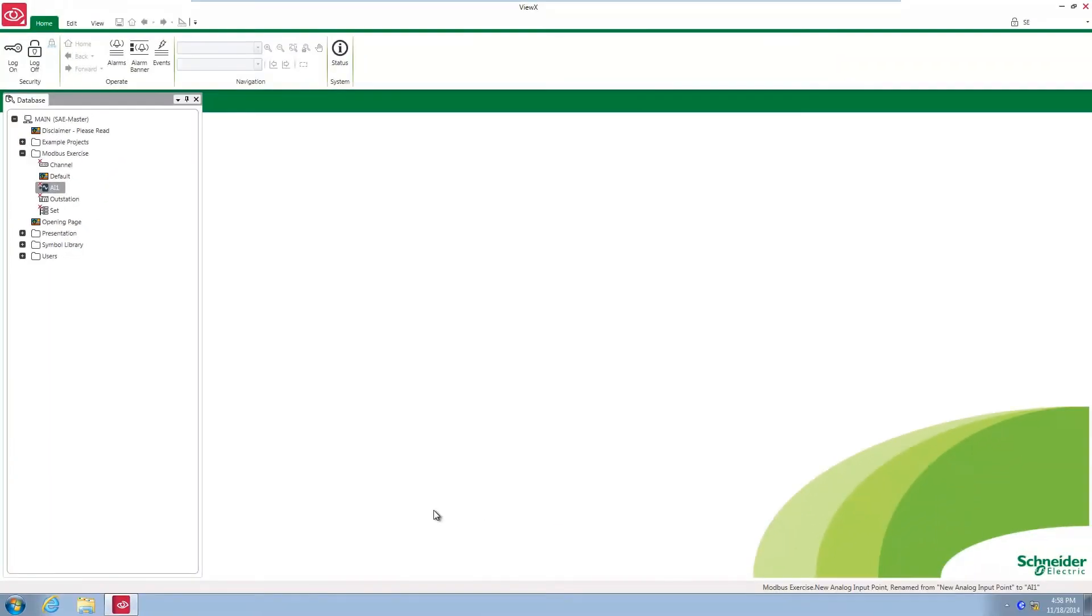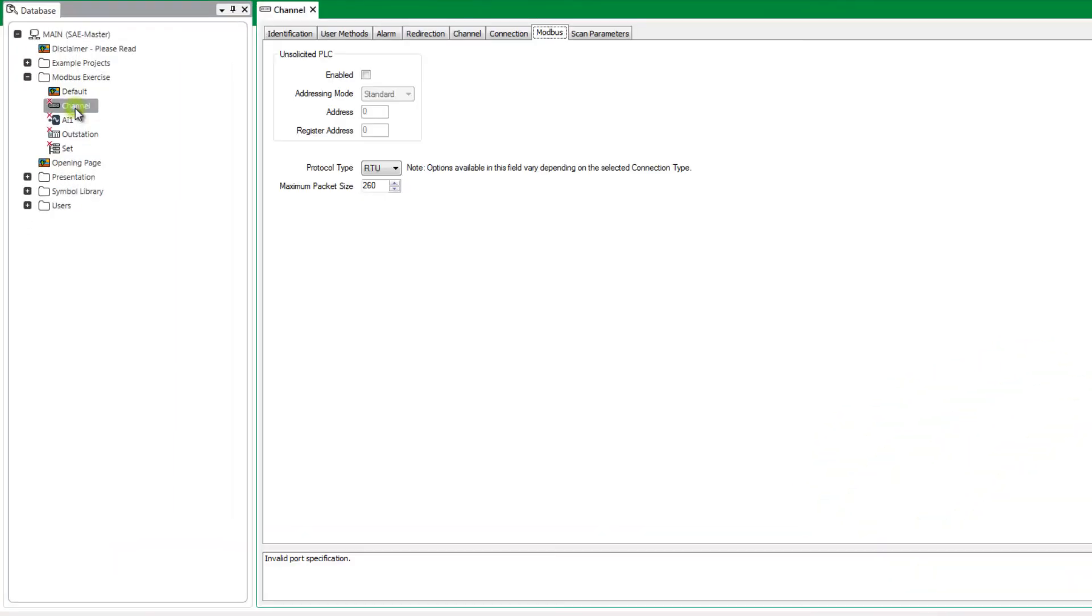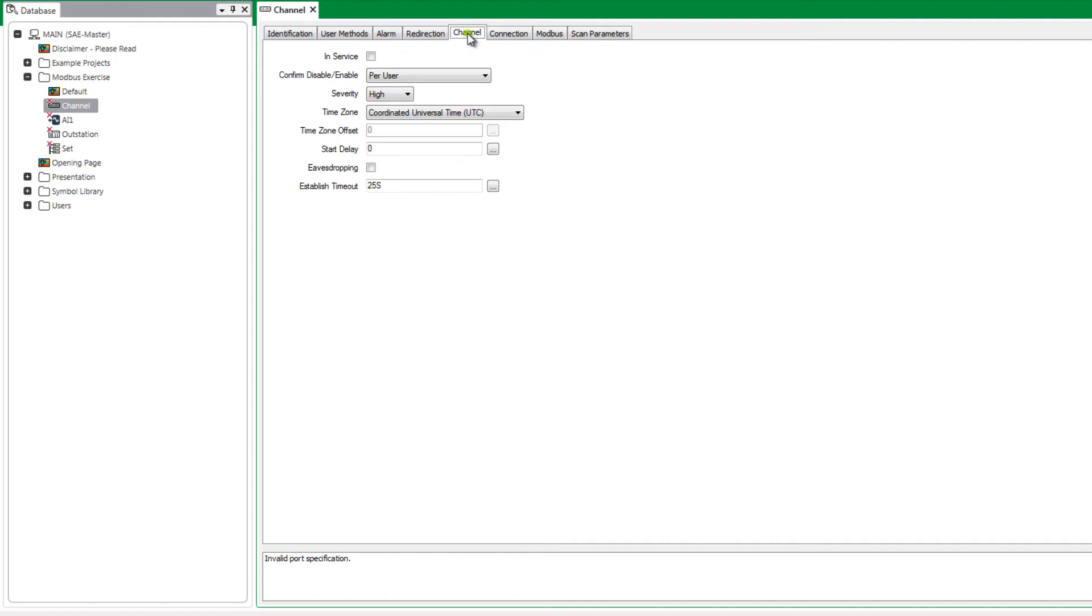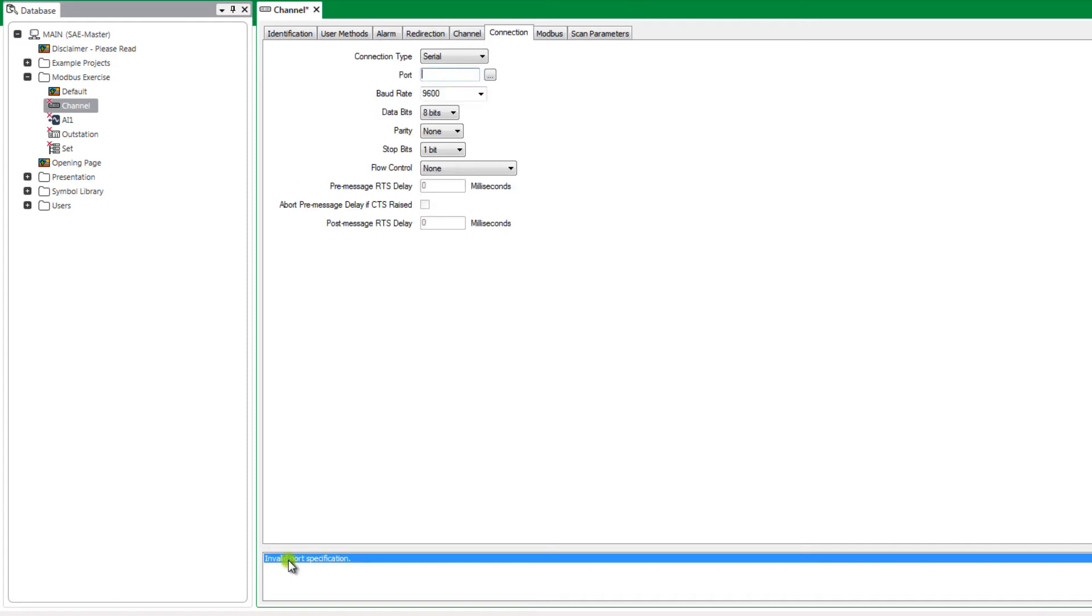The channel is the object that defines the basic communications channel that will be used by ClearScada to talk to the device. This may be a serial port or TCP IP connection. In the database tree open the channel object, go to the channel tab and put it in service. Next double-click on the error message displayed below. ClearScada will always display the configuration errors and this will always take you to the location of the configuration error.